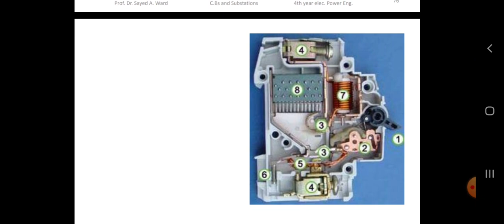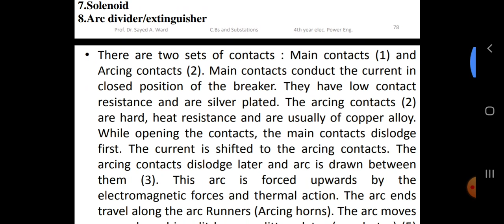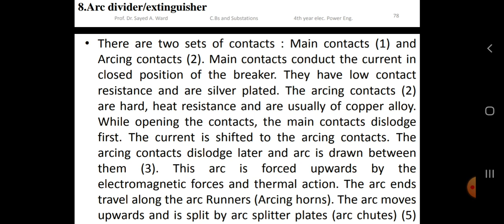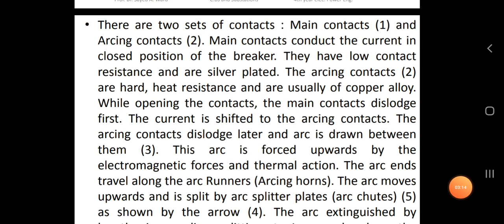So these are the figures of the circuit breakers. There are two sets of contacts, main contacts and arcing contacts. Main contacts conduct the current in the closed position of the breaker. They have low contact resistance and are silver plated. The arcing contacts are hard, heat resistant, and are usually of copper alloy. While opening, the main contacts separate first, and the current is shifted to the arcing contacts. The arcing contacts separate later and the arc is drawn between them.